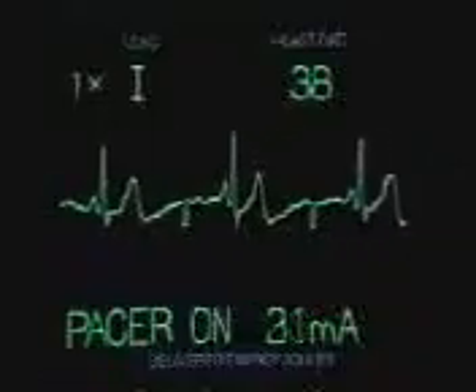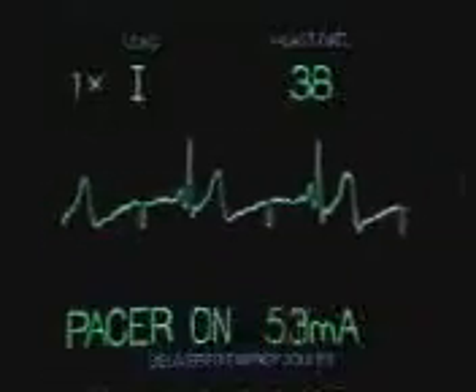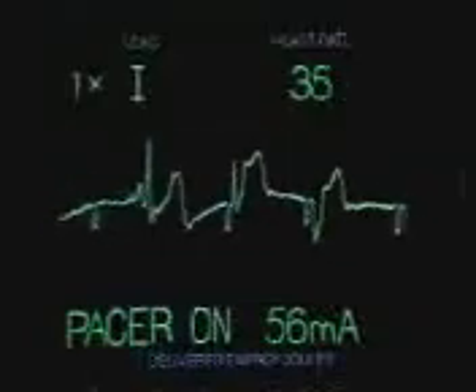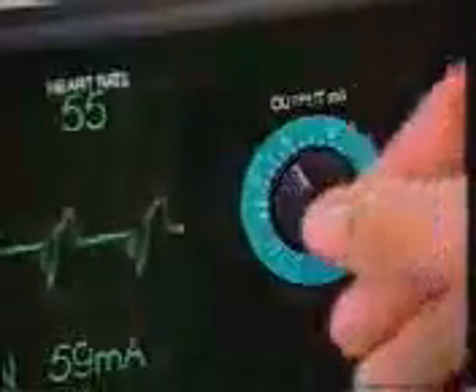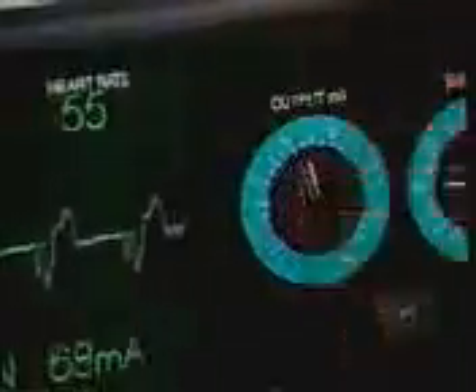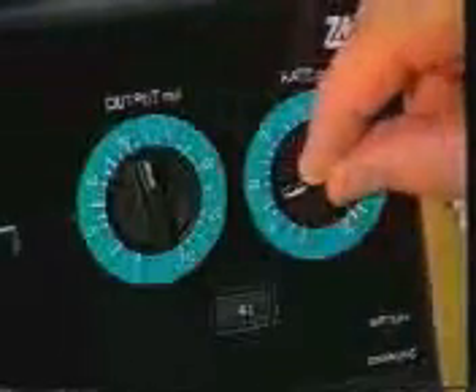To use the ZOLL PD in standby mode, first establish effective pacing. Note the milliamps and run an ECG strip to document morphology at capture. Set milliamps 10% higher than capture. Turn the pacing rate to below the patient's heart rate. This will suppress pacing unless the patient's own rate drops below the set pacing rate.